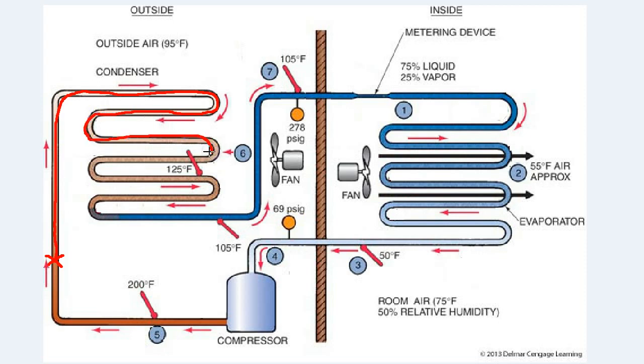To get it to a certain point in the condensing coil, we may be 50-50 vapor liquid. As we continue to remove latent heat, we are going to eventually get to a point in the condensing coil where we are 100% liquid. We can't change state anymore because we are at 100% liquid, and we are now at the beginning of the subcooling part of the condensing coil.